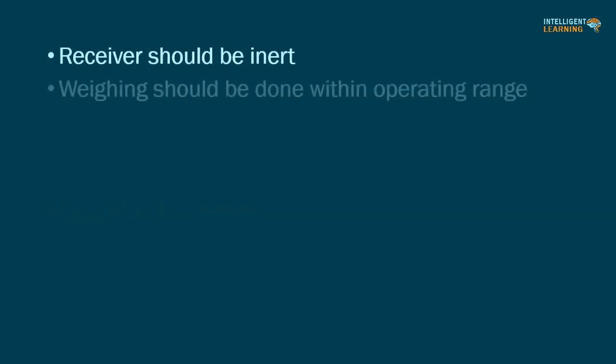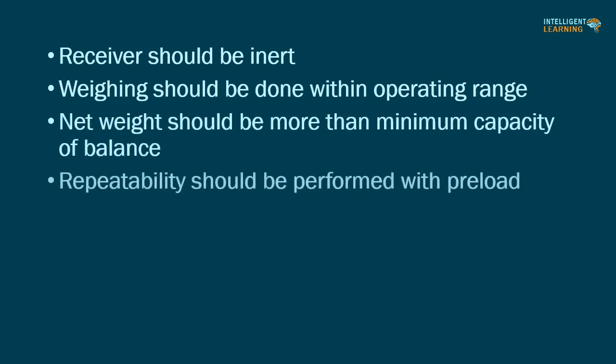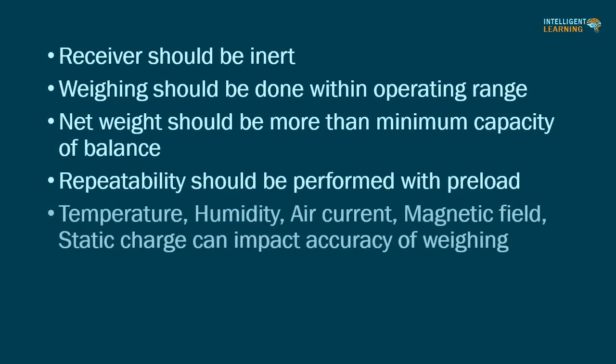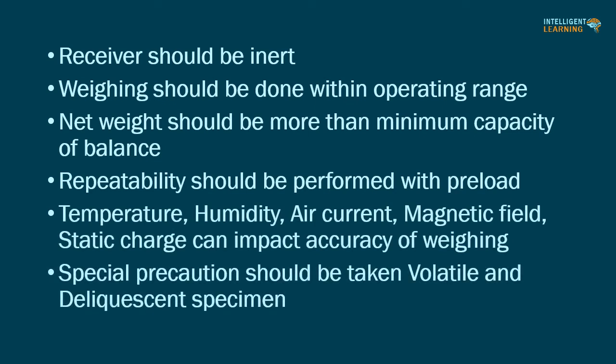Quick recap of this video: receivers should be inert; weighing should be done within operating range; net weight should be more than the minimum capacity of the balance; repeatability should be performed with preload. Temperature, humidity, air current, magnetic field, and static charge can impact the accuracy of weighing. Special precautions should be taken for volatile and deliquescent specimens.